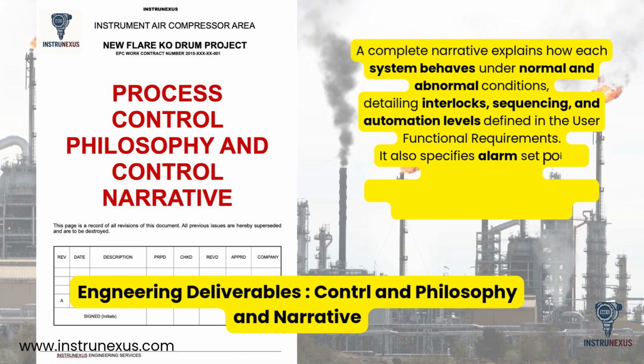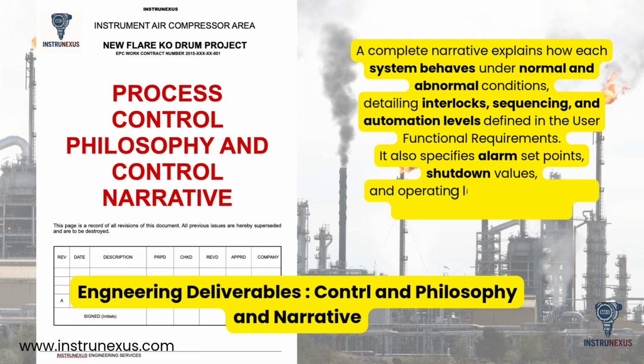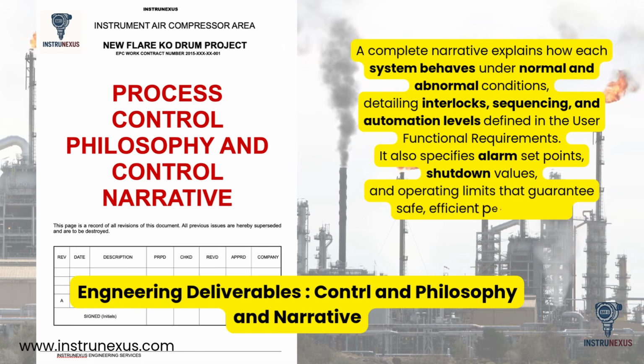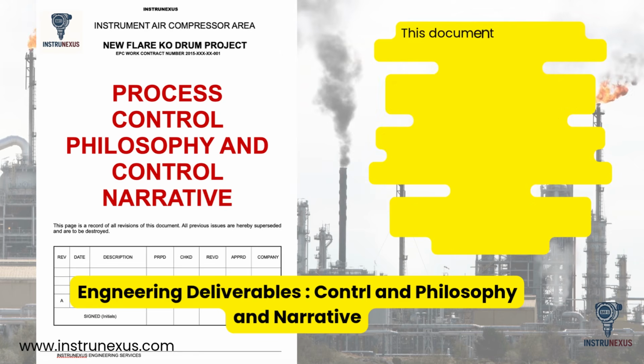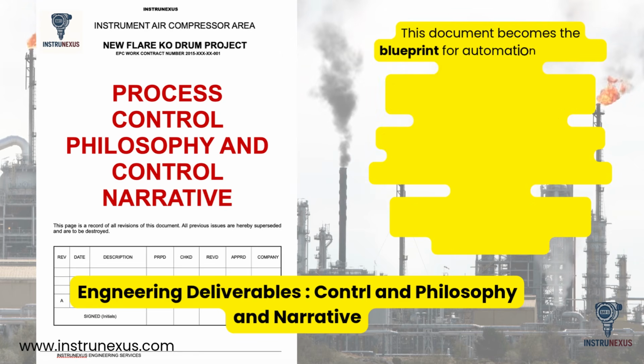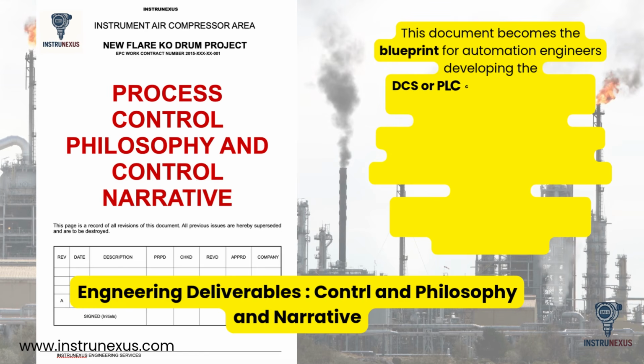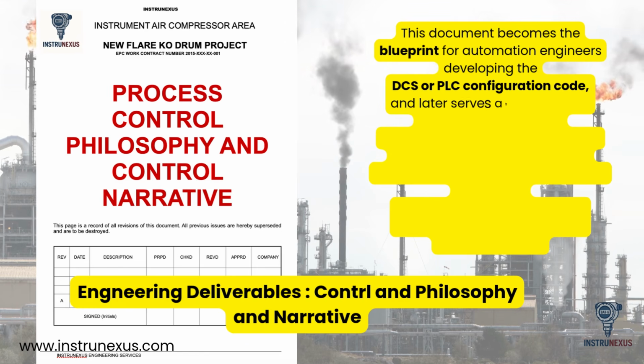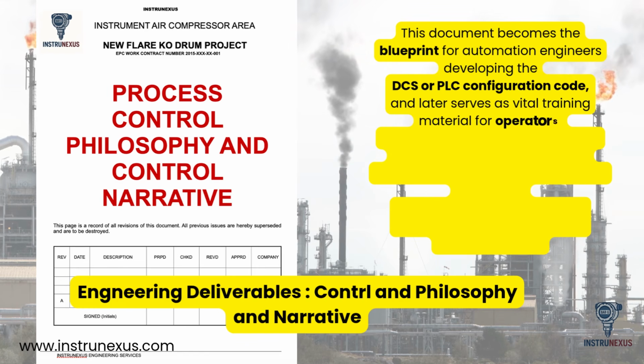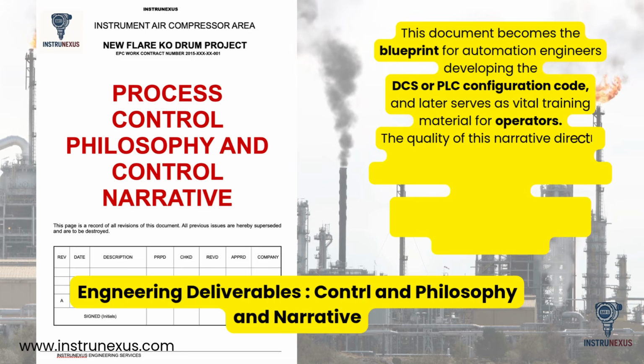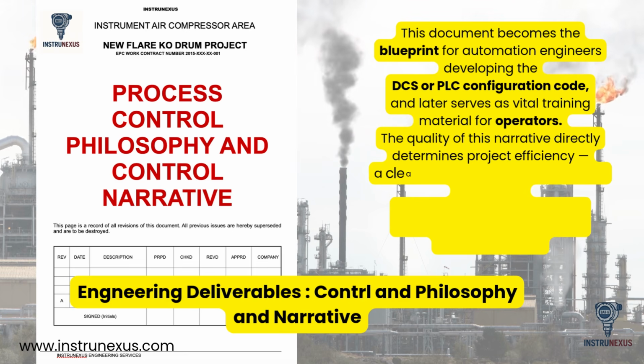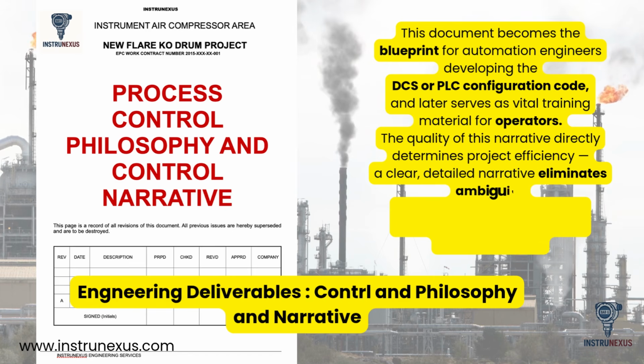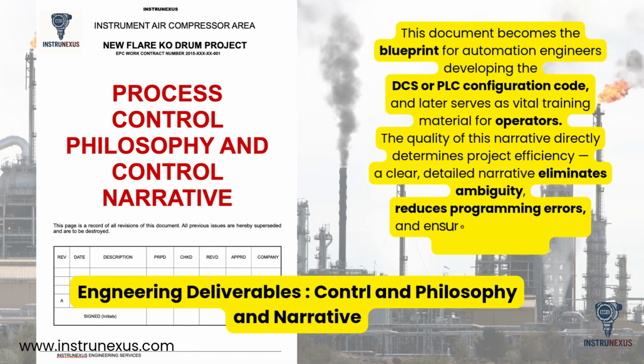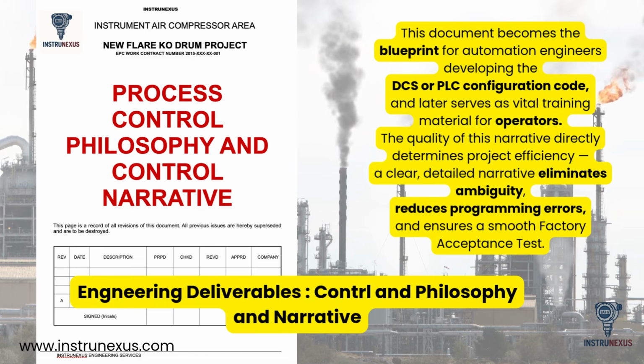It also specifies alarm set points, shutdown values, and operating limits that guarantee safe, efficient performance. This document becomes the blueprint for automation engineers developing the DCS or PLC configuration code, and later serves as vital training material for operators. The quality of this narrative directly determines project efficiency. A clear, detailed narrative eliminates ambiguity, reduces programming errors, and ensures a smooth factory acceptance test.